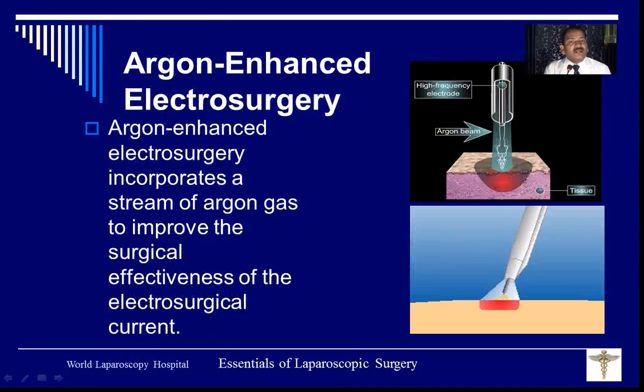Now we will discuss some of the new generation equipment. One instrument is called Argon Enhanced Electrosurgery. As we know, fulguration is very good. Why is fulguration good? Because it can spray the tissue without doing a deeper injury. But the problem is it can only go up to 0.5 millimeter distance. So the scientists thought how to increase the capacity of fulguration, and then this argon beamer was invented.